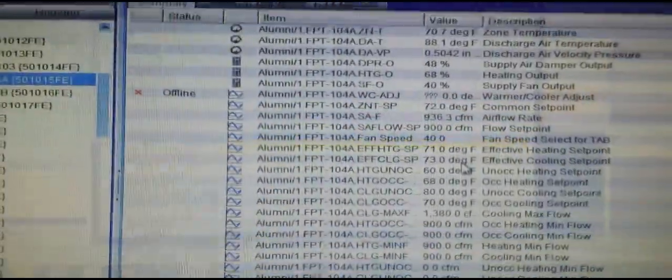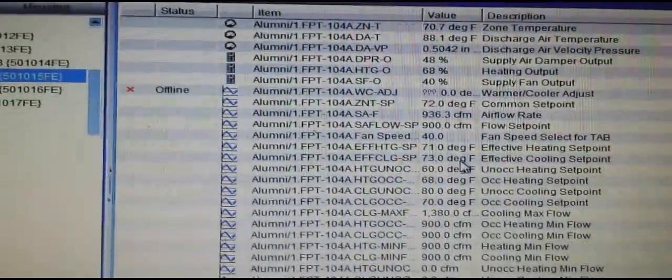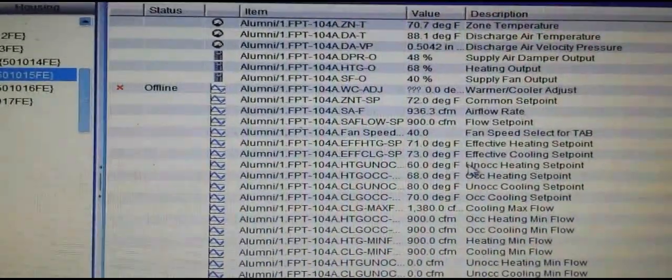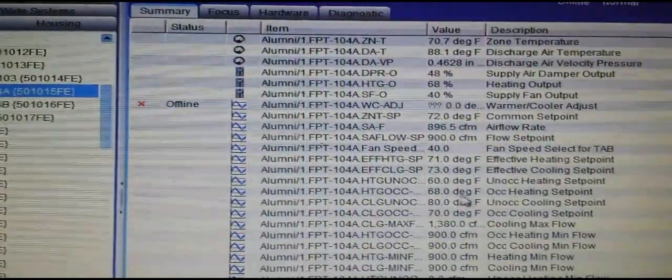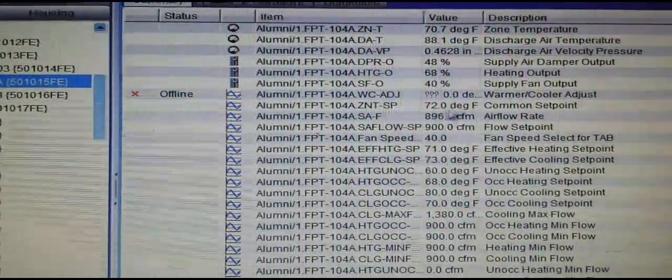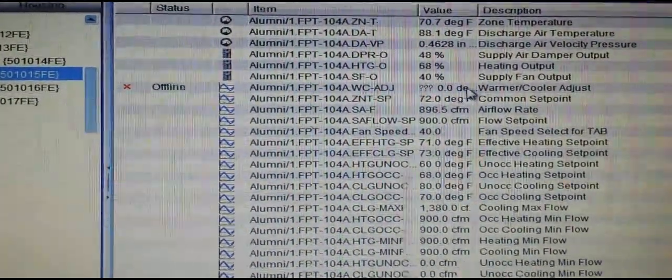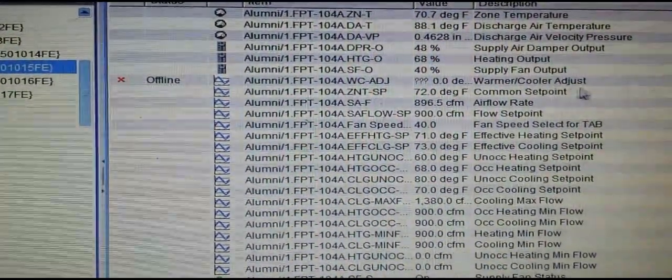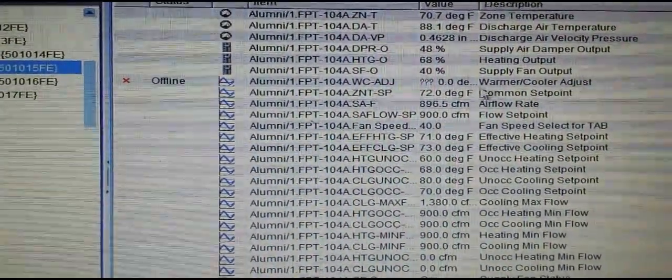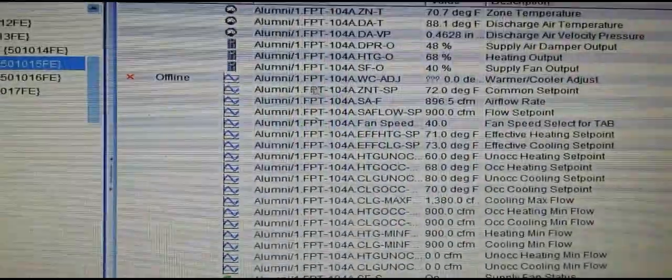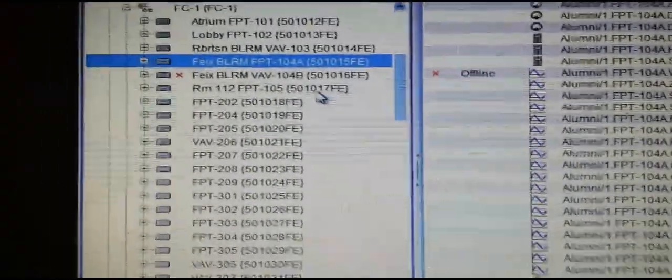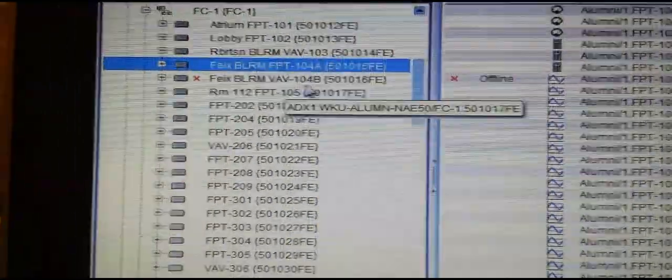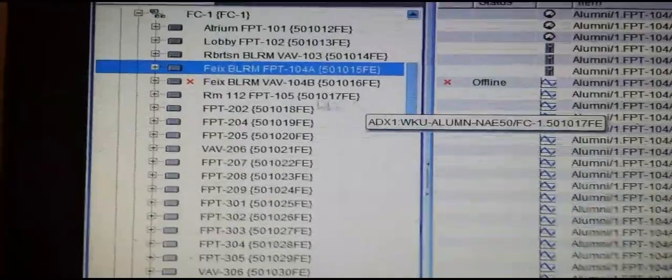One thing you'll notice within Metasys Extended Architecture: once you make that change, the warmer/cooler point will come up as being offline since it is no longer in the program. Metasys does not know how to interpret it.